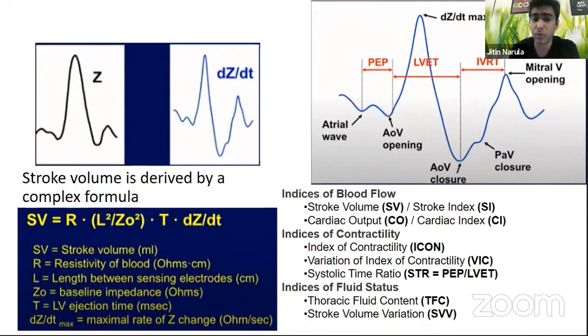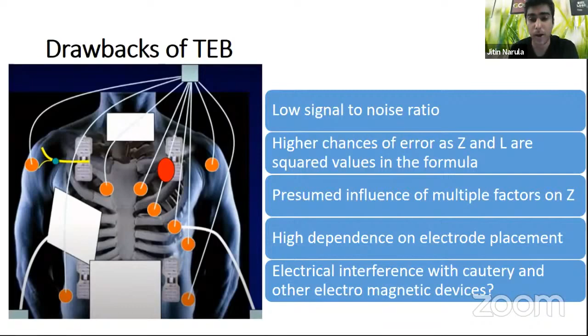However, there are certain drawbacks with the use of this technology, and these include low signal to noise ratio, a higher chance of error, as Z and L are the squared values in the formula, and presumed influence of multiple factors on the chest, like central lines, intercostal drainage tubes, external wires, external monitoring cables, dressing pads, and high dependence on electrode placement, and presumed electrical interference with cautery and other electromagnetic devices. So a bioreactance cardiac output technique was subsequently developed to improve the signal to noise ratio issues with the thoracic electrical bioimpedance.